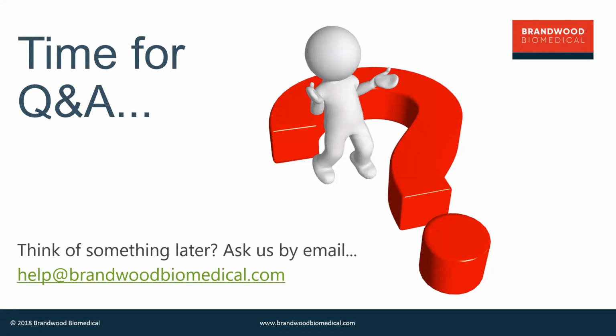Well, I think the answer, Geraldine, is this: the certificate for foreign government or a free sales certificate, depending on which you're getting it from, is a statement from the national government that the product is able to be legally supplied. So if you currently have a product registration and an ISO 13485 certificate, then you are on the market and you can still get your CFG. If you go for an MDSAP audit and you get a 6, it means you're not going to get your MDSAP certificate, but presumably the ISO 13485 is also going to be struggling at that point.